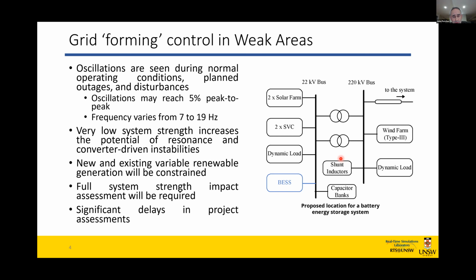Specifically the use of real-time systems with control hardware in the loop to de-risk some fairly large investments in equipment. This particular example is looking at a grid forming battery energy storage system connected into a weak area of the grid. Weak in Australia is pretty much very weak by anyone else's standard. This particular system is a few hundred kilometers down a transmission line from pretty much nowhere to nowhere.